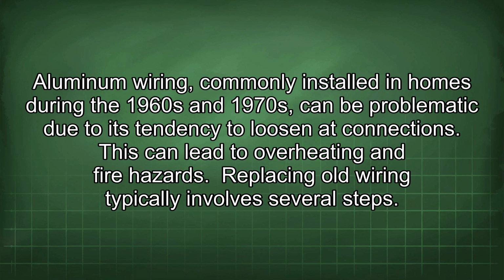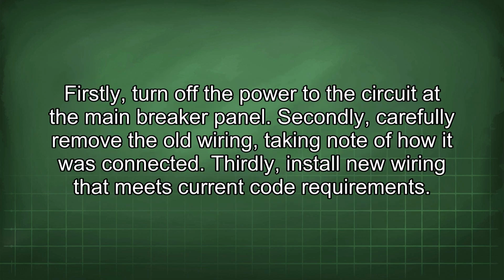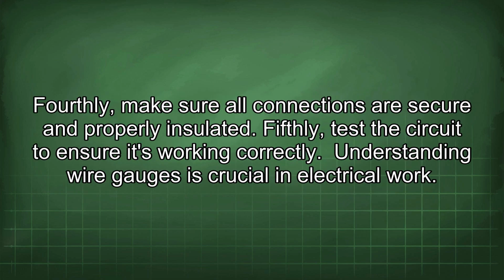Replacing old wiring typically involves several steps. Firstly, turn off the power to the circuit at the main breaker panel. Secondly, carefully remove the old wiring, taking note of how it was connected. Thirdly, install new wiring that meets current code requirements. Fourthly, make sure all connections are secure and properly insulated. Fifthly, test the circuit to ensure it's working correctly.